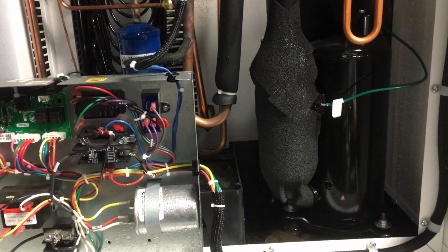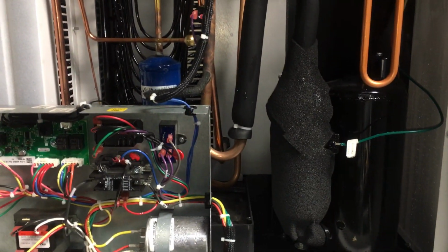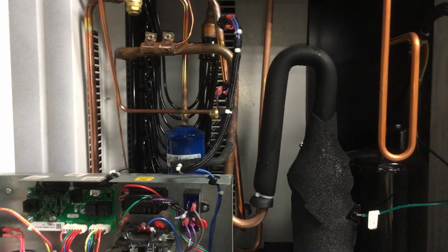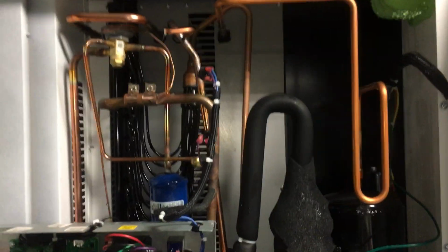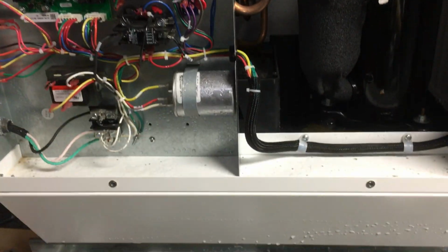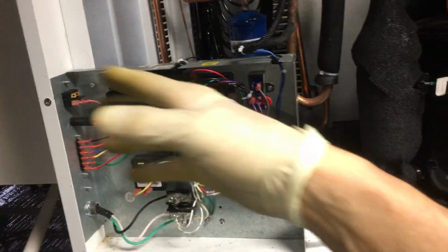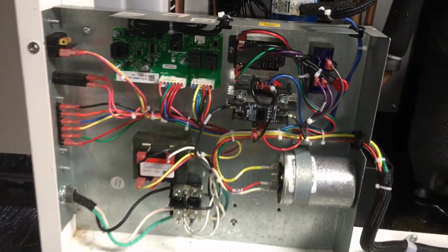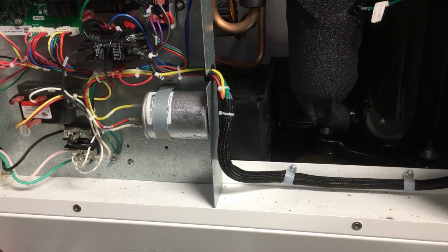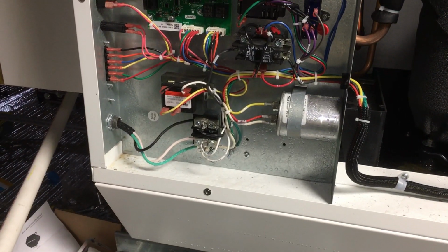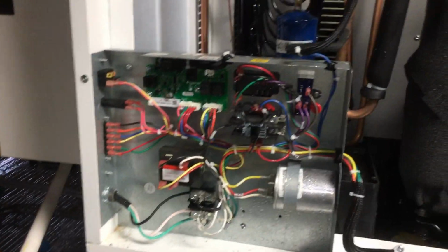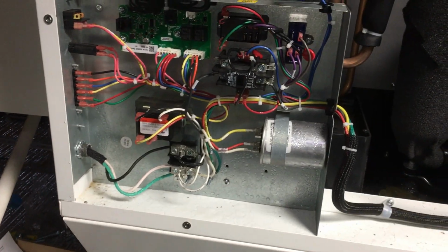It started before the managers who came over and took over this project, and this was all determined before they contacted me, because if they would have contacted me, I would have had them raise the roof of their room another 5 or 6 feet or more, which was easier and cheaper to do than all of this. Up here with all the extra ducting, you have another $50,000 in ducting, and then you have another $18,000 in labor to install the 3 dehumidifiers, and all that could have been avoided by adding say 5-6 feet to the roof height, which was much cheaper and faster.